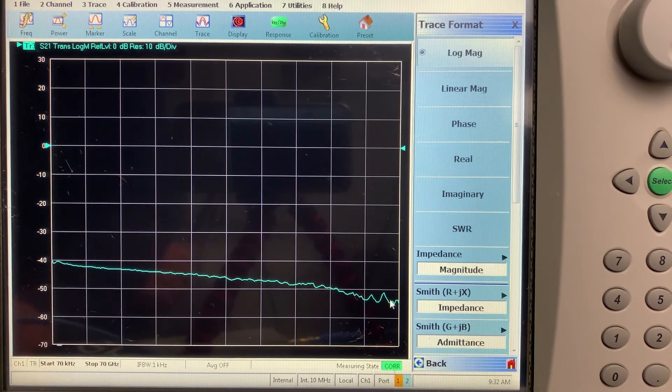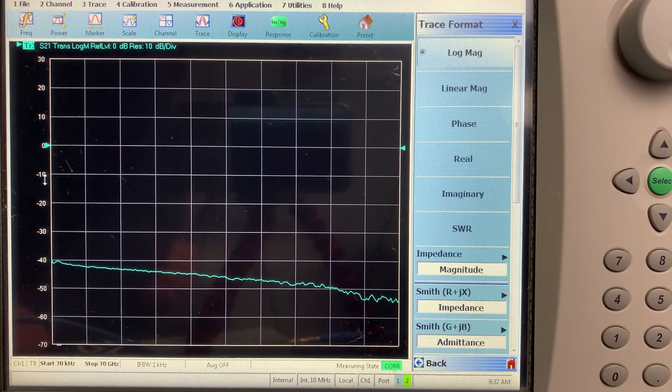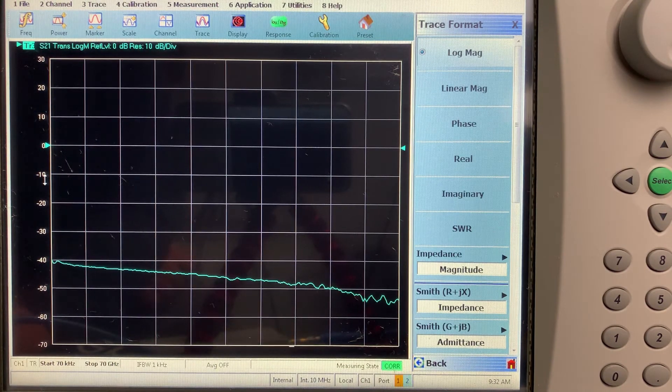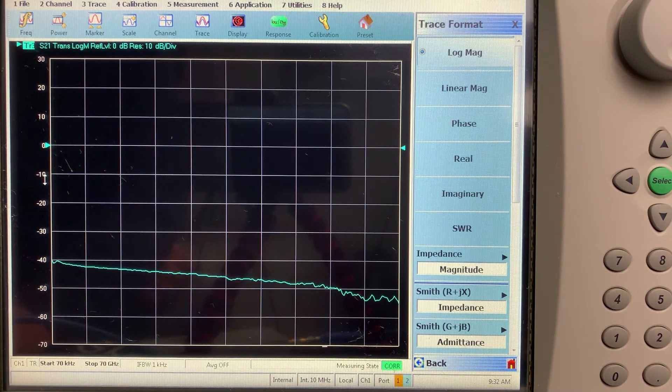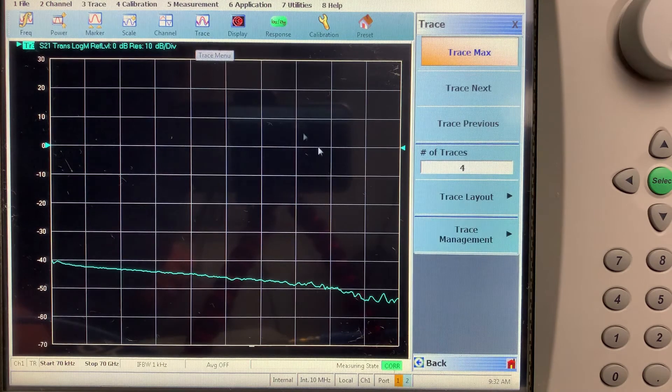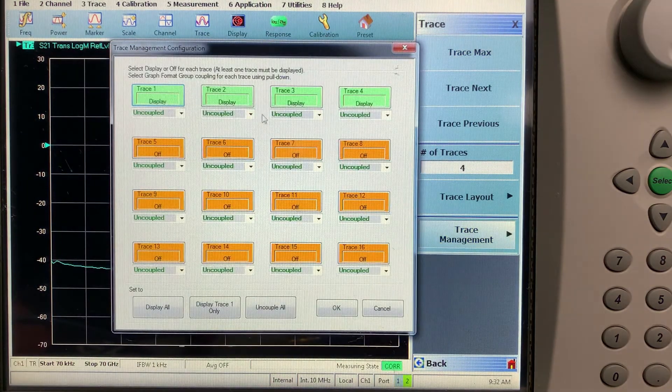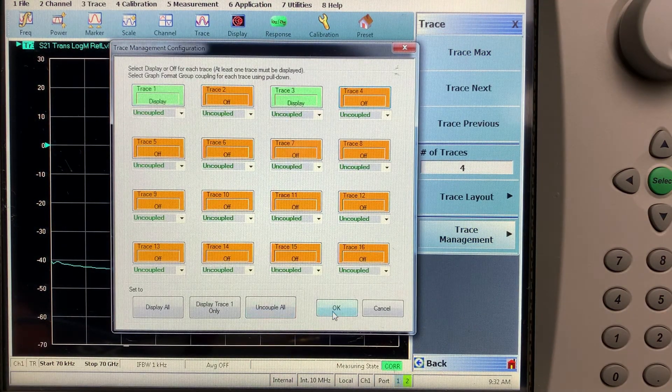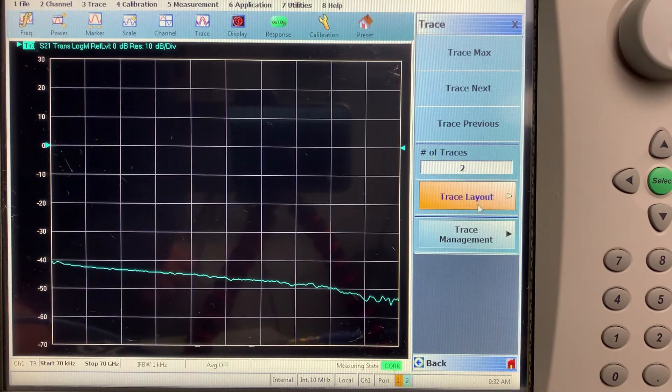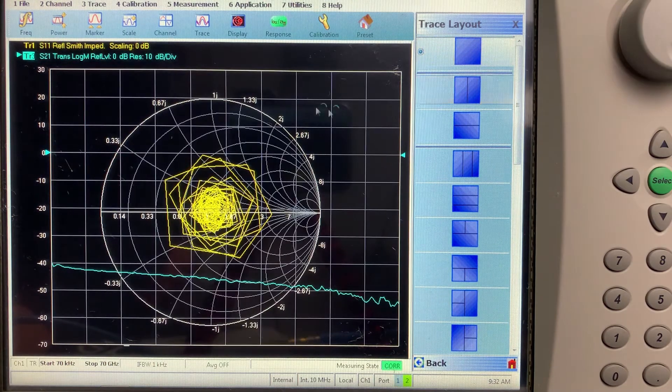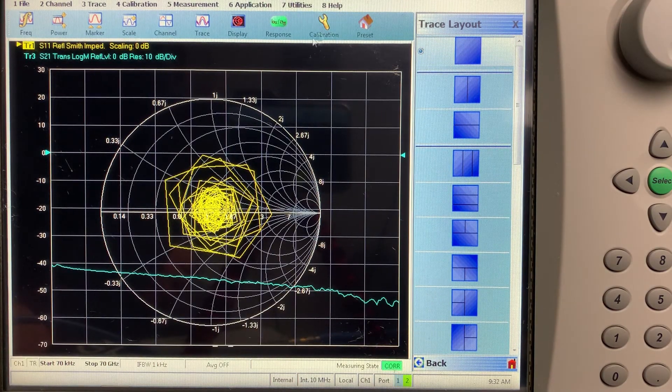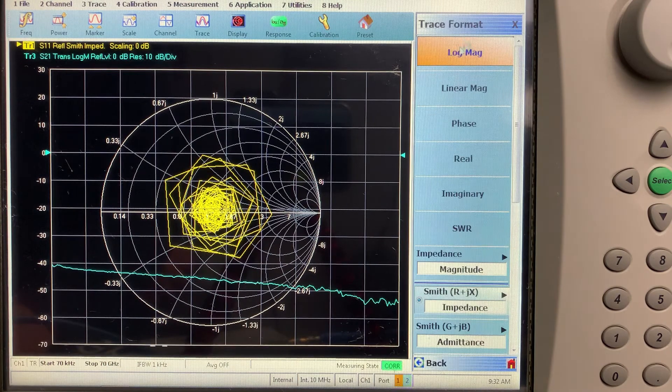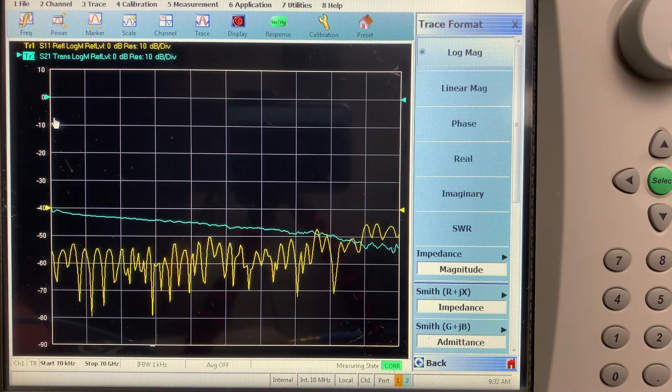We can also manipulate our traces so that we can look at S11 simultaneously, the input match of the RF in of the E2O converter. So we use our trace menu here. Trace management. We can turn off two and four. Press OK. Go to trace layout. Overlay this one. This one one. Change the display to log mag.